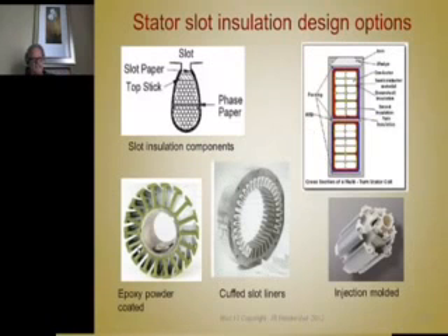Here's an example of the core that's been fluidized, coated with that epoxy, ready to wind. This happens to be a DC armature. This one here is a case of molded glass-filled nylon piece that goes halfway down the slots, and one identical to it goes down the other end of the slots, and so you wind your coils around this. This is a stator on the inside, but this can all be done as a stator on the outside as well.